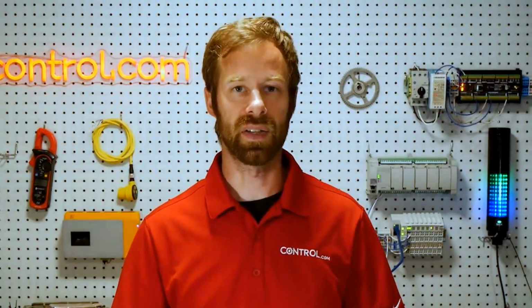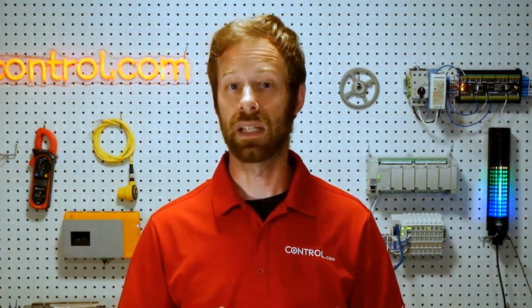Which is better? Well, we can't say which is better in automation. We very rarely can. If we have the luxury of being able to afford a better system, then yes, we should look to the future and say, what can we install into this system that allows us to not only control but also collect data and make things better? If we don't have that continual luxury or a greenfield application, we can still look at some of these hybrids, the ones that, like IO-Link, allow us to replace a discrete sensor with another sensor, but they also provide the ability to collect much more information and change things as we go, so we can continue improving the system over time. So I encourage you to look at your system, decide what fits the best for you.